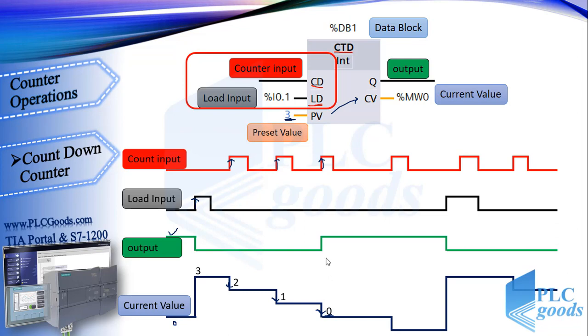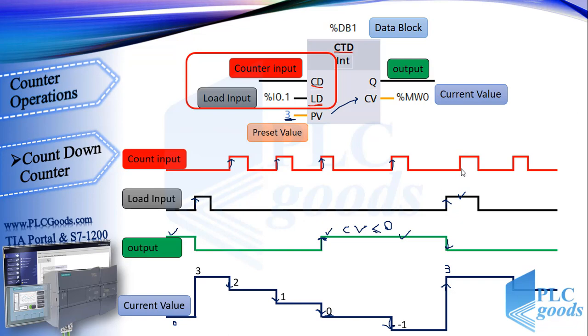At this moment the output changes to on. For this counter, the output will be on if the current value is equal to or less than 0. With next pulses, the current value decreases and the output remains on. When we have another positive pulse at the load input, it transfers the preset value to the current value and turns off the output. Like the previous counter, if both inputs are activated, the load command takes priority over counting.